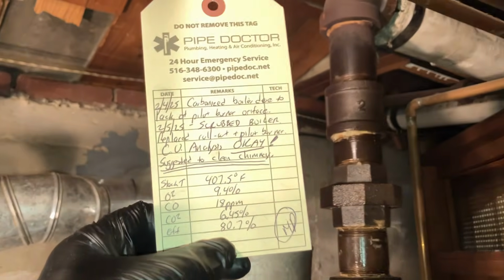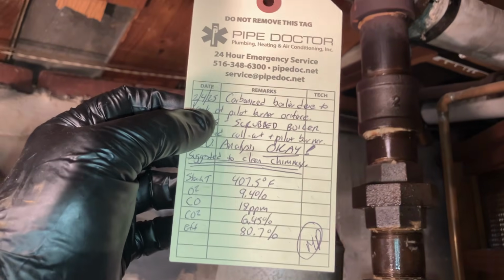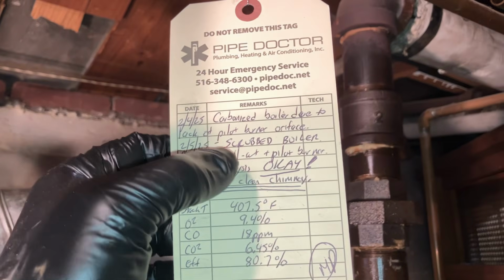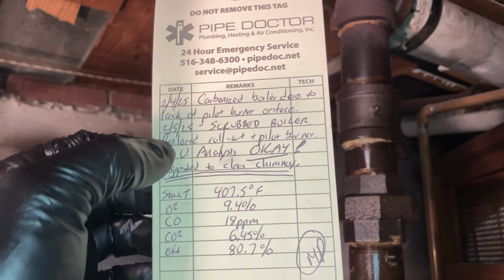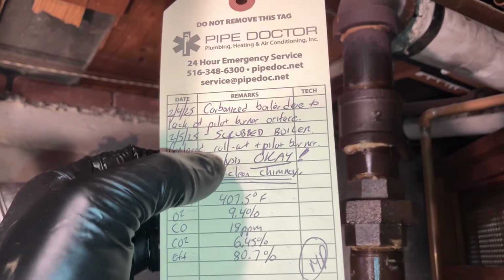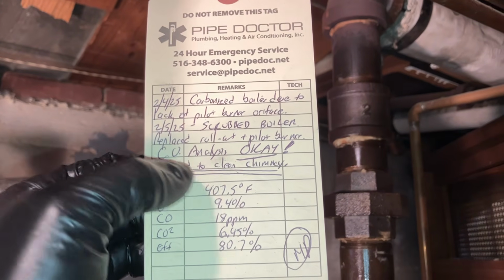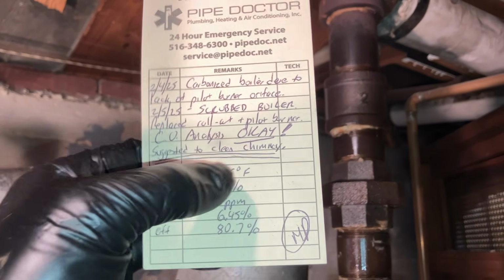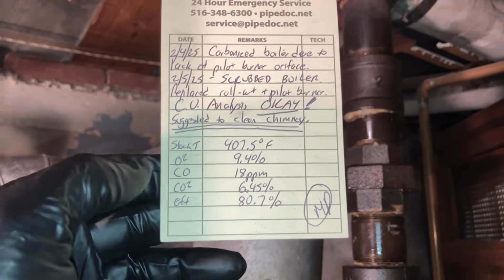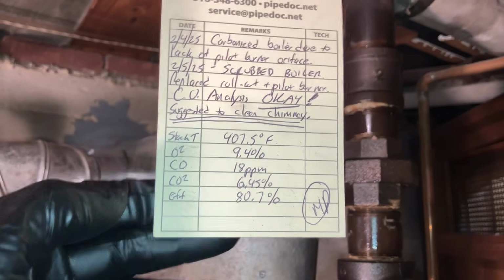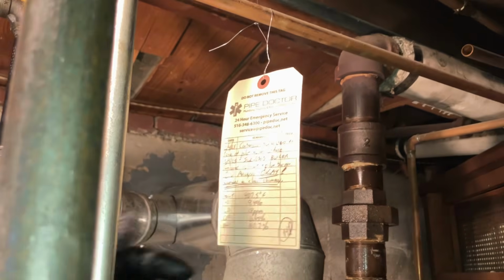I've updated my service ticket. I was here yesterday, carbonized boiler due to lack of pilot burner orifice. Today, the 5th of February, scrub the boiler, replace rollout and pilot burner, CO analysis, okay. Suggested to clean chimney, and there's all of our readouts in case that disappears. And we'll fill this in on subsequent service calls.